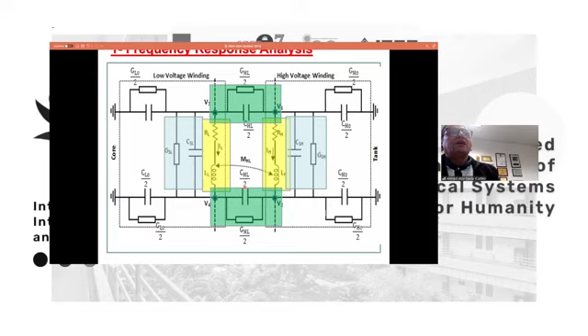But between the low voltage winding and the core, of course, we must have insulation, that's varnish on the laminated steel, and paper insulation. Again, any insulation can be represented by a capacitor. And all of these windings are immersed in oil. So the oil can be represented by a capacitor and dielectric conductance. So that's the equivalent circuit of a simple disk or turn. Okay? Frequency response analysis came from this equivalent circuit.